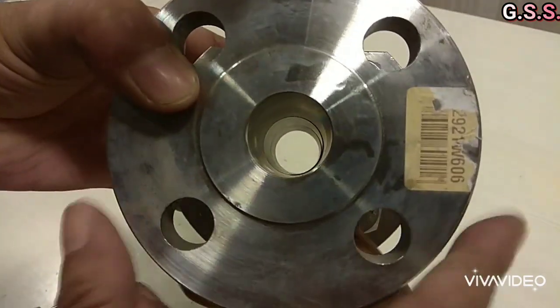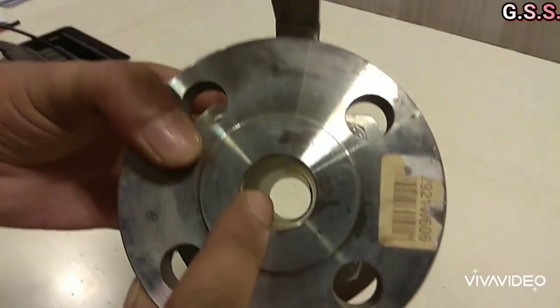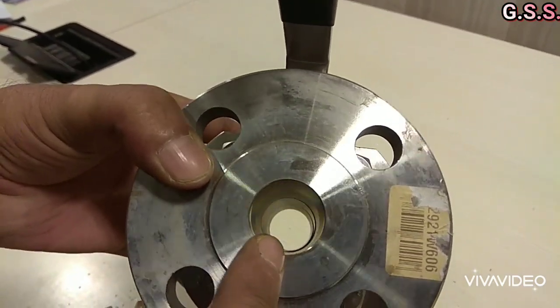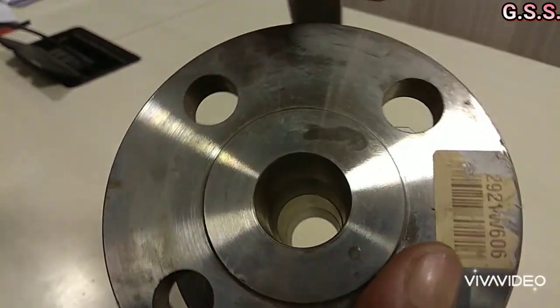For this valve, the flange ID or pipeline ID and the bore ID on the ball is the same. That means this valve is a full bore valve.